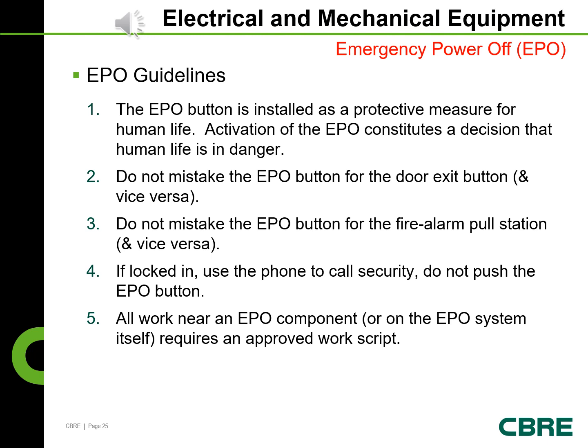Electrical and mechanical equipment, emergency power off EPO. EPO guidelines. The EPO button is installed as a protective measure for human life. Activation of the EPO constitutes a decision that human life is in danger. Do not mistake the EPO button for the door exit button and vice versa. Do not mistake the EPO button for the fire alarm pull station and vice versa.